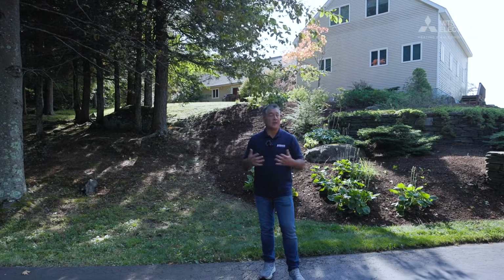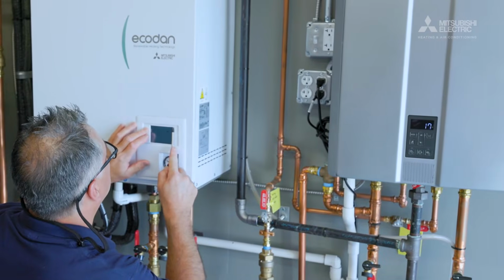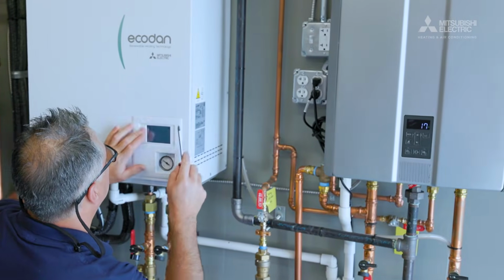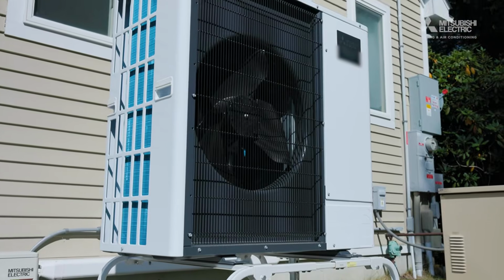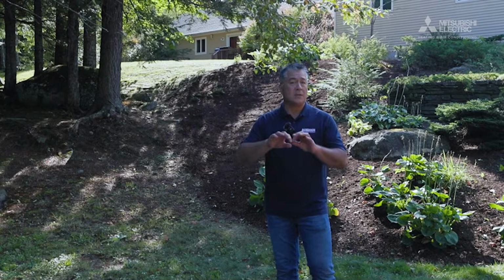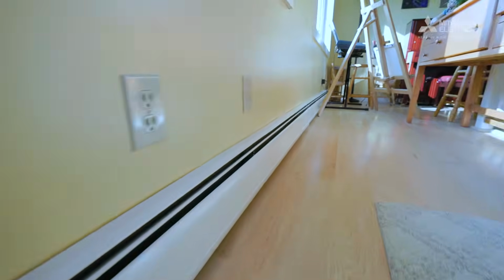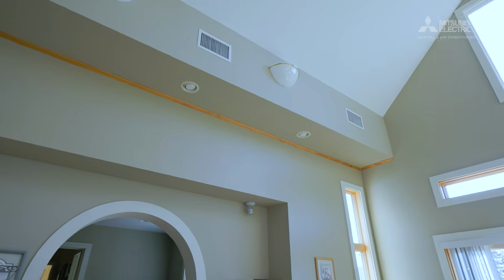Mitsubishi Electric has an Ecodan air-to-water heat pump that has a very high hot water output temperature of 158 degrees Fahrenheit. What that allowed us to do is to use all of our existing baseboard radiation and any other delivery devices that we had, so we didn't have to do any interior renovation.